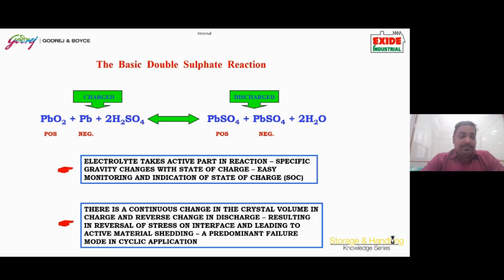At the positive plate, as I told you, it is constructed with lead oxide, PbO2, which reacts with H2SO4 during charge condition. So in a fully charged battery we have PbO2 plus Pb plus H2SO4. That's why we measure the voltage across PbO2 and Pb, where Pb is the negative plate. The voltage should range around 2.15 to 2.17 in the open circuit condition.